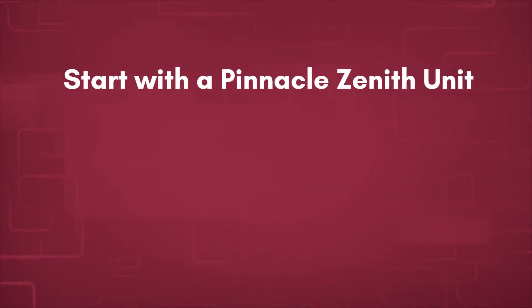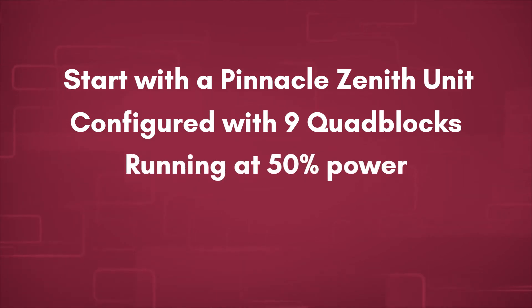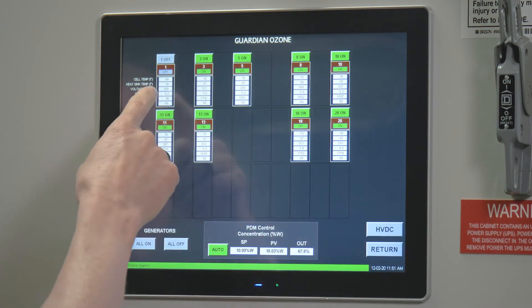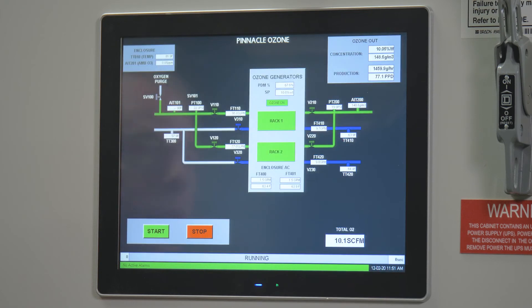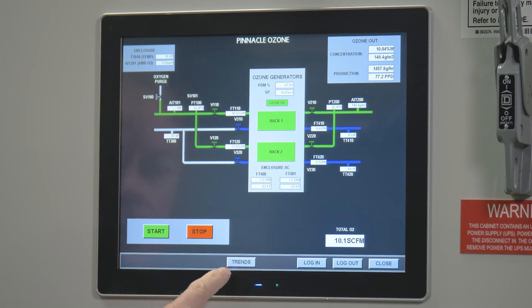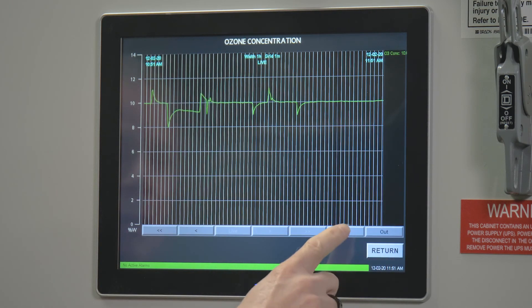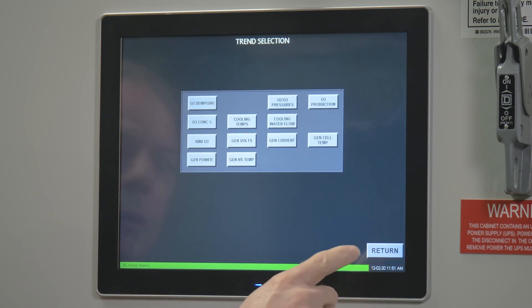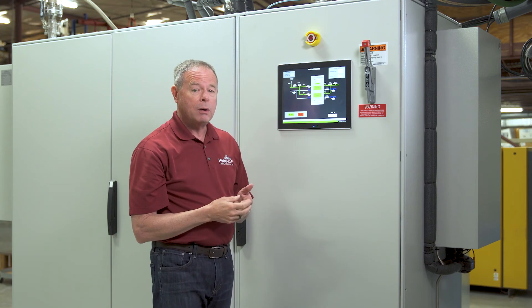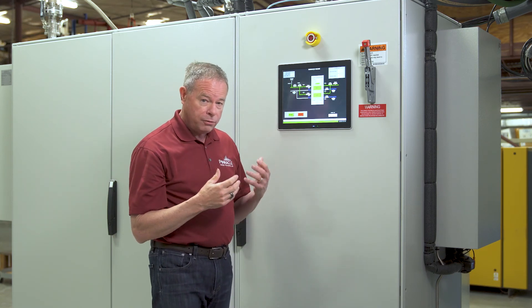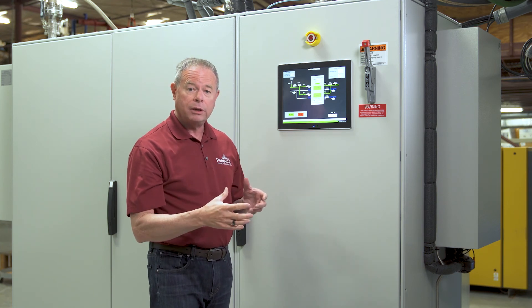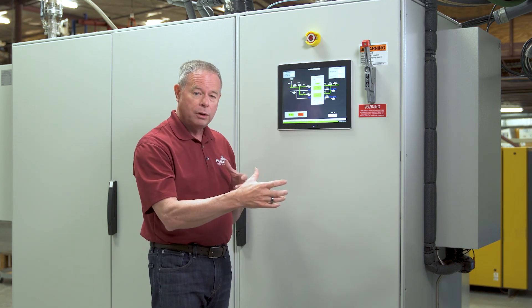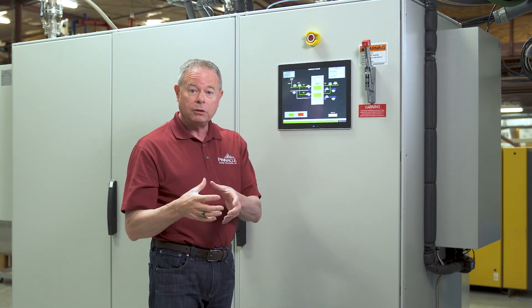So let's recap. We start with a Pinnacle Zenith unit configured with nine quad blocks running at 50% power, producing 77 pounds of ozone a day at 10% concentration. We simulated a failure by physically turning quad block number one off and looked at the response. We go to trends, O3 concentration — there's the failure right there. You can see a nice exponential response. The system recovered gracefully. The system was running at 50% power, and now with one quad block failed, the remaining eight quad blocks have to run a little bit harder to get that 10% concentration — 67.4% output power — making up for the ozone lost from the failed quad block.